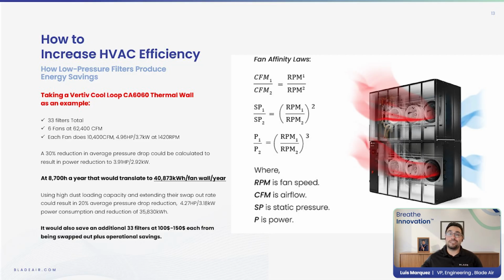A low pressure, high dust holding filter may start at the same 0.3 inches of water column, but under the same pollutant concentrations, it may reach 0.8 inches of water column in 6 months instead of that recommended 3. Using the affinity laws on my right and not really going into 100% of the detail of the calculations, we can show that if we leave the same frequency of change at 3 months, this would result in about a 30% reduction in pressure drop, and that in turn results in 21% fan energy savings.